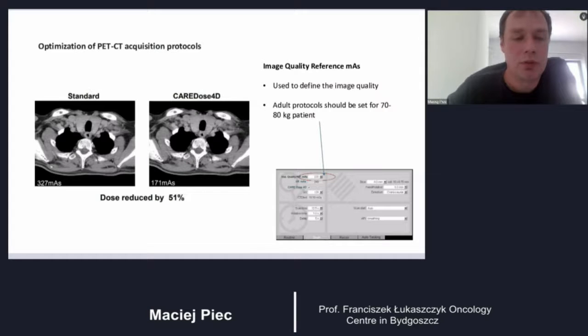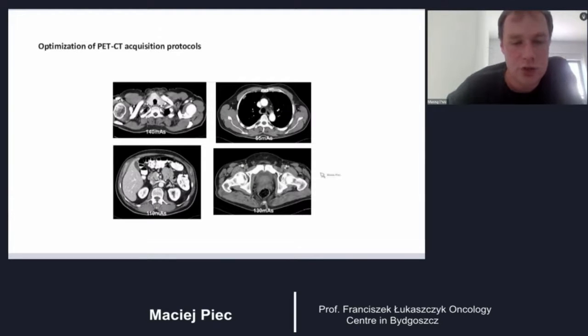When we use such dose modulation, the dose can be reduced even by 51%. Where the equipment needs to emit more radiation, it will do it. Where it can reduce the dose automatically, it will do it as well. So these systems are very much recommended. There are different settings for children and for adults.